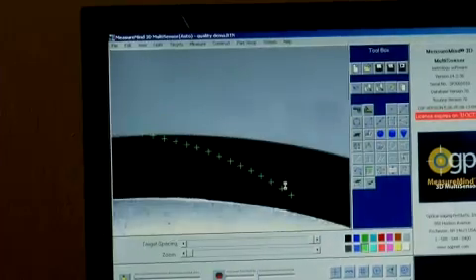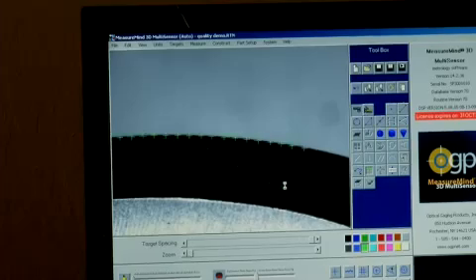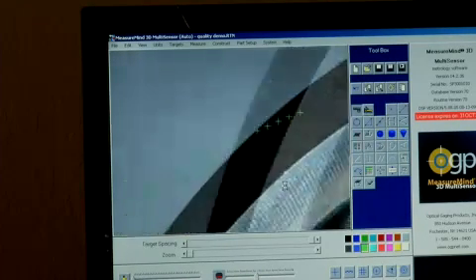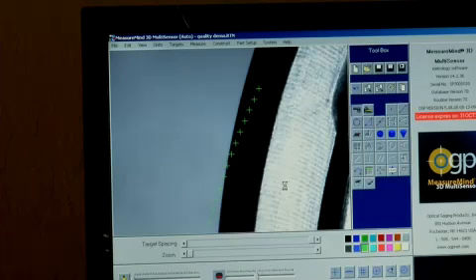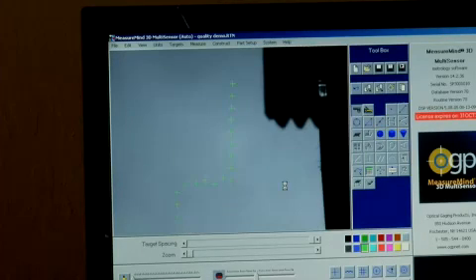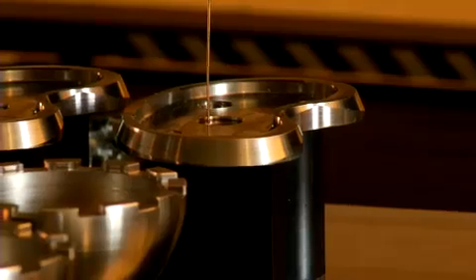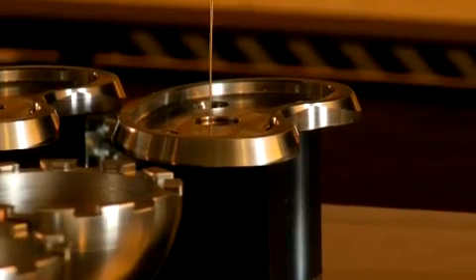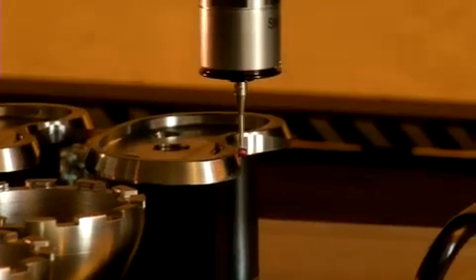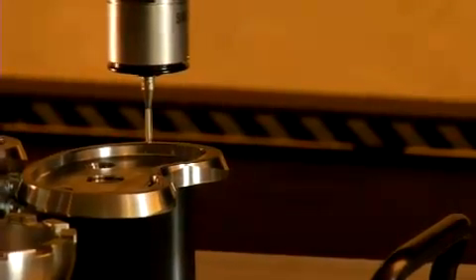High-accuracy edge measurements can provide quantitative visual feedback on 2D and 3D measurements. Video measurement excels at measuring contrast change where surfaces intersect. It is also one of the faster sensors for XY measurement, as it can take many points instantly in one field of view. A tactile probe is more appropriate for surface measurement of internal features.